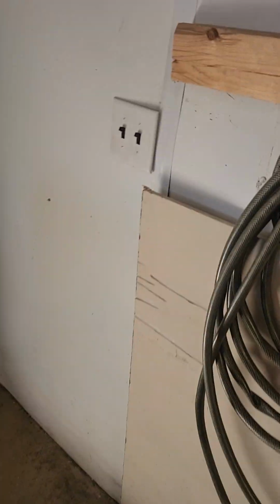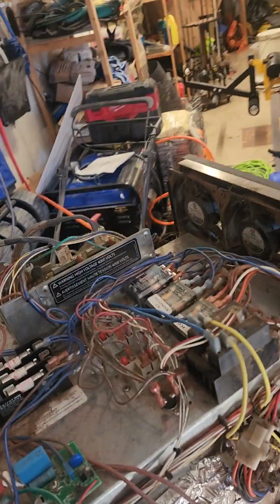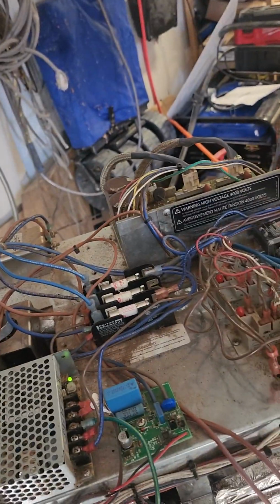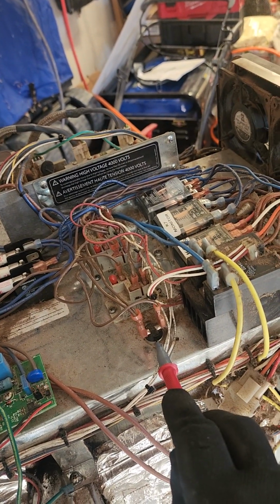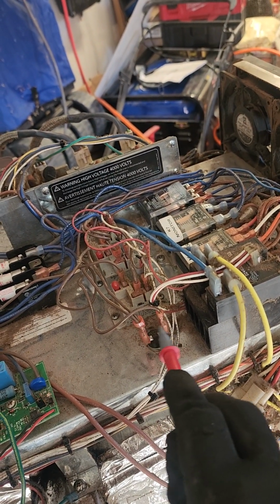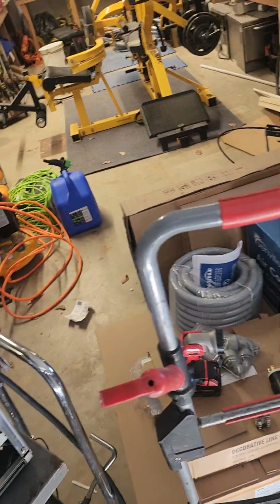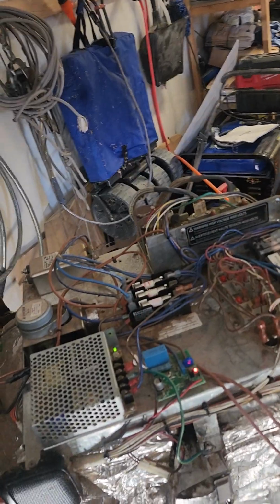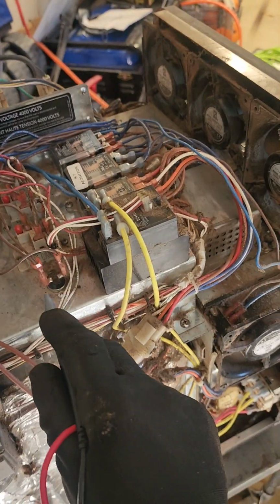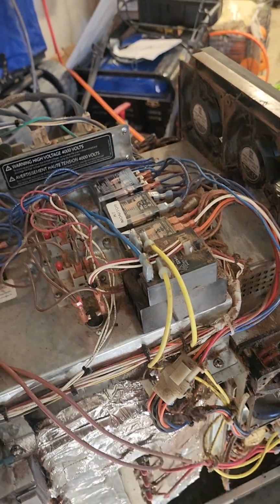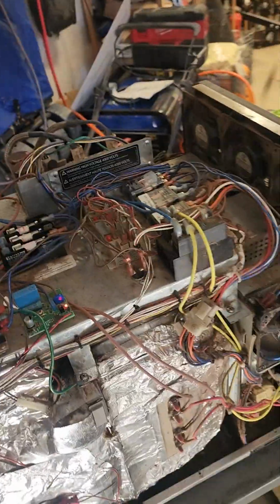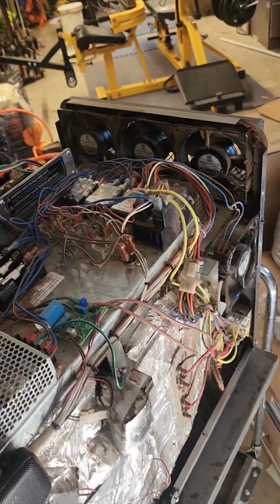The way you check those, once the oven warms up, this little thermostat right here will get hot and it'll close these two wires and turn those fans on. Just for testing purposes, you could take a jumper wire and jump between there so you can test the fans before you give the client an estimate, not have to warm the oven all the way up. And that's it. That's everything.